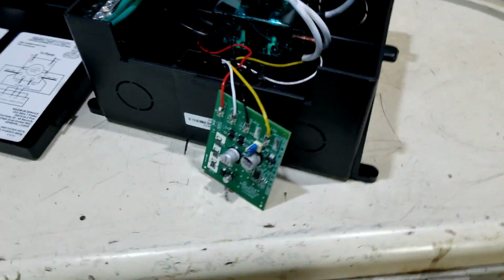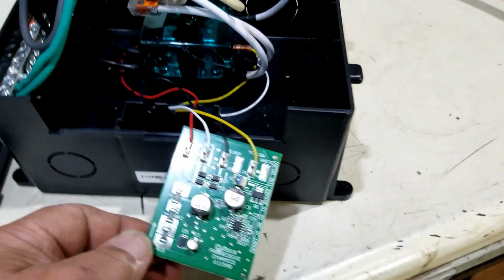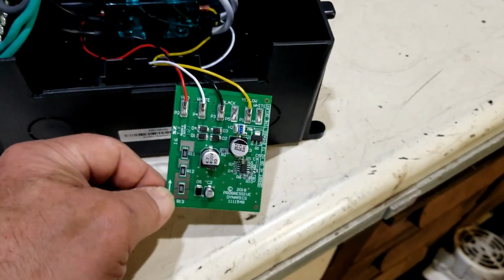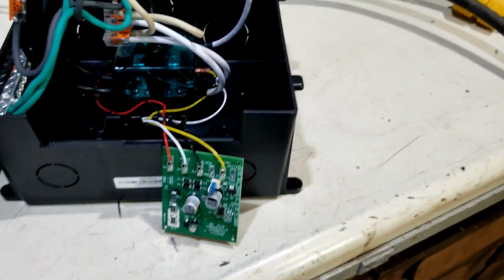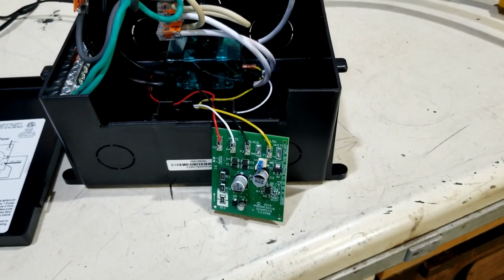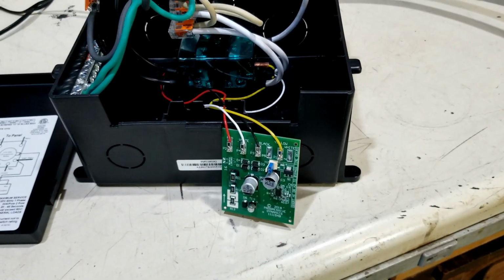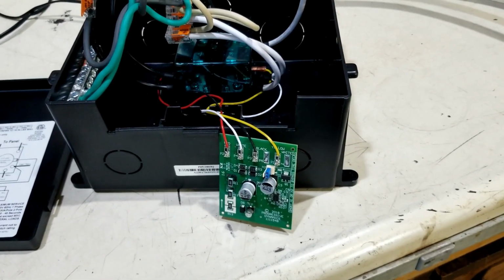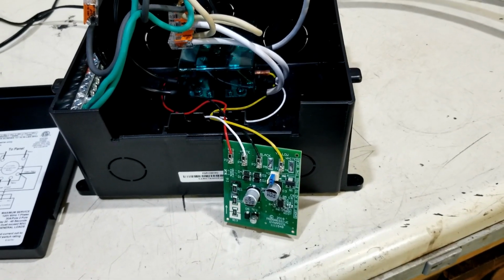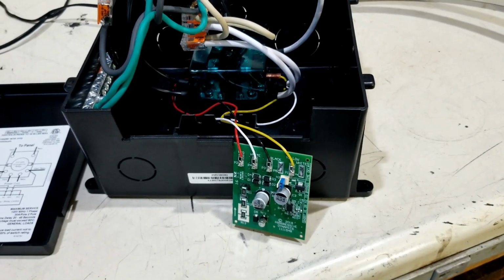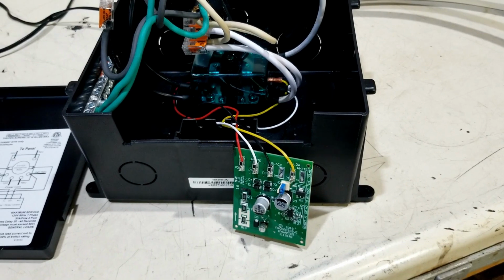The reason for this time delay circuit, if you're operating with the generator, is to give that generator 20 or 30 seconds to power up, stabilize a little bit, and start to warm up before you engage a load.